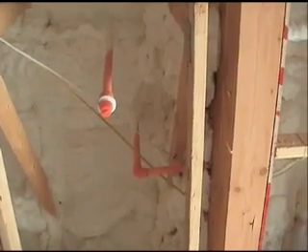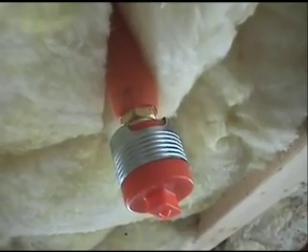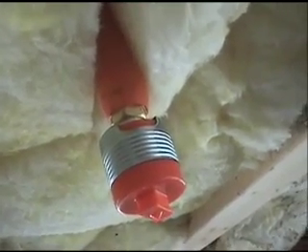One common misnomer about a fire suppression system is that if one sprinkler goes off in the house, all of the sprinklers go off throughout the house. That causes quite a few people to worry about putting a fire suppression system into their personal residence. However, the new systems that have come out over the last 5 to 10 years don't have that problem. Basically, if you have a fire anywhere in the house, only the sprinklers that have heated up to over 135 degrees will actually discharge and let water out. So you really won't have a problem throughout the rest of the house unless the fire happens to spread to other areas, causing other sprinkler heads to release.